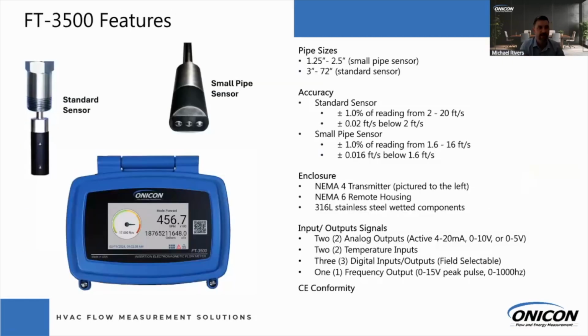All right, now to dive into the FT-3500. So this is suitable from 1¼ inch to 72-inch. There are two different sensor types. We do have one for the smaller pipe sensors. Also, for accuracy, it's a 1% of reading device. We'll dive into the accuracy on the next slide. The enclosure is NEMA 4, so you can actually put the transmitter outdoors if needed. And then the actual sensing element is a NEMA 6, which could be submerged if necessary. And then lastly, output signals. You have the two analogs, temperature inputs, pulse inputs and outputs, or standard frequency output, and then network communication that we'll talk about in a little bit.